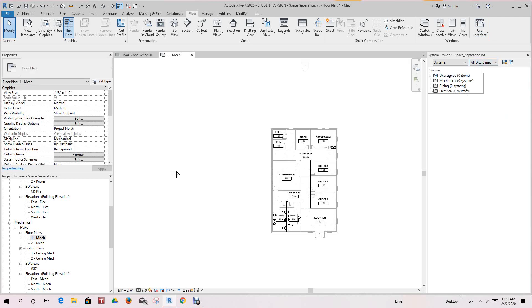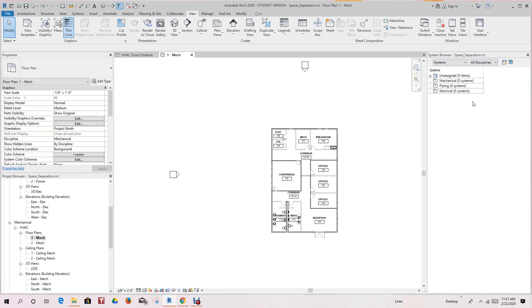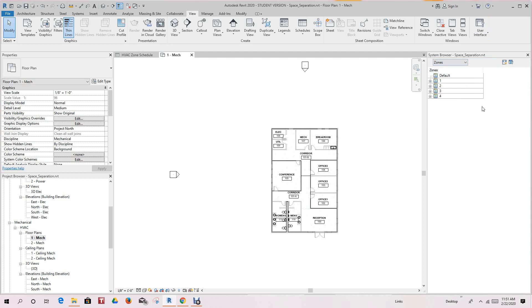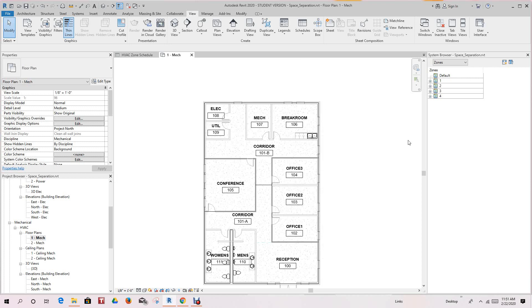Right now we're looking at systems. You can see mechanical, piping, electrical, and we don't have any systems because we didn't create any. Now click the dropdown to the right here. You have an option called Zones. Click Zones, and now you're listing zones that we created. You do have one default zone. Every Revit project you create has a default zone, and by default all your spaces belong to that default zone unless you create a new one.